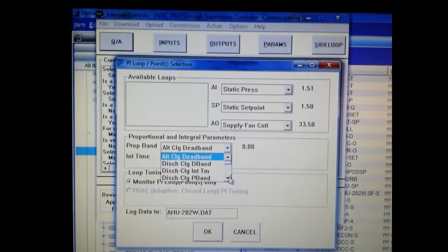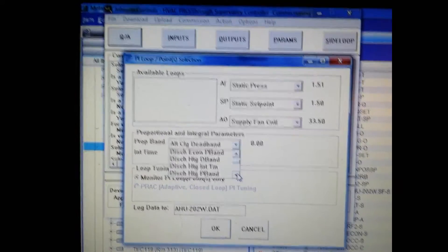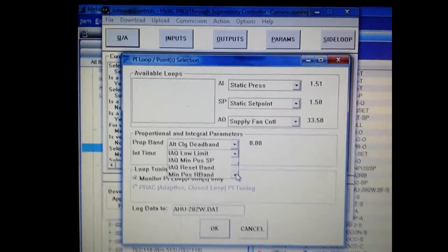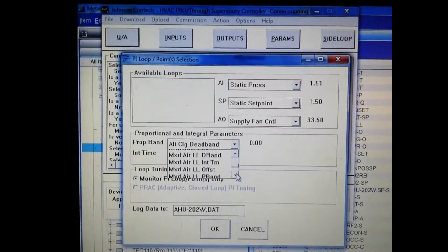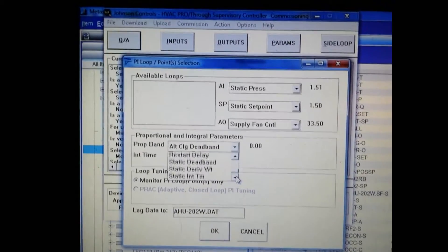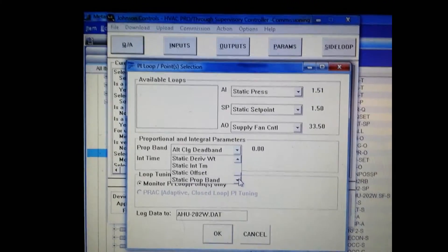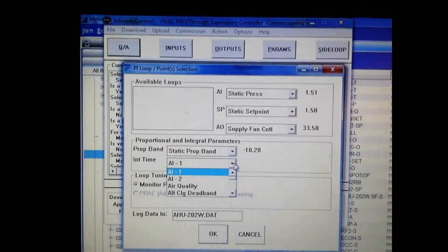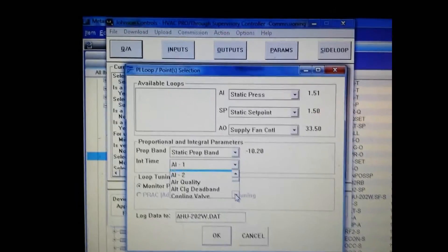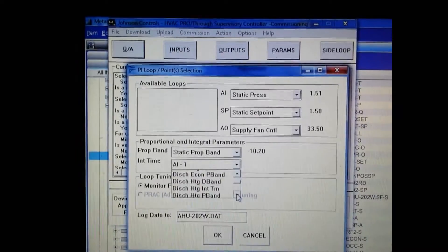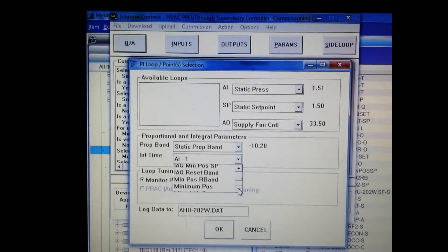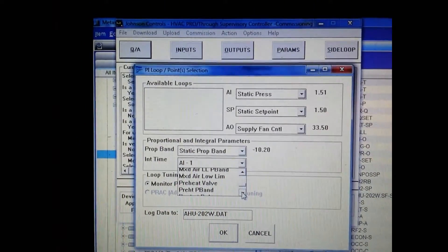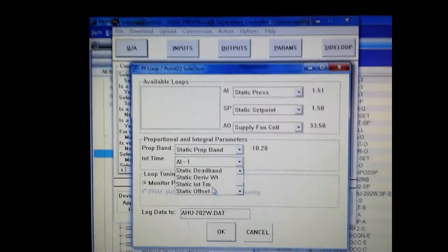Now the values that we are going to be changing are the proportional band and the integral time. So from our drop down menu we have to select the appropriate prop band within our program for the supply fan. And of course the integral time is going to be the same - it's going to be the supply fan integral time. So we select that as well from the second menu.